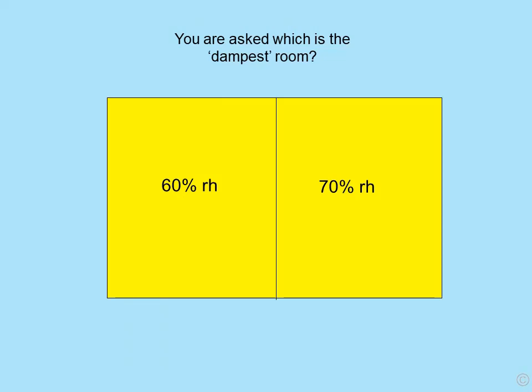If somebody presents two RH readings — 60% and 70% — and asks which is the dampest room, the answer is simply: you don't know. You cannot say, because the temperature is unknown. It may simply be a temperature factor.